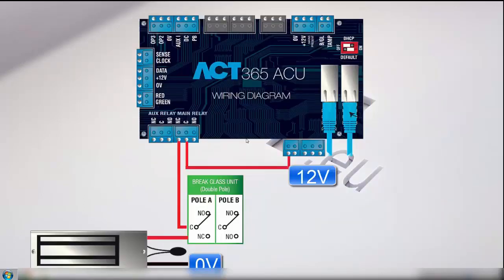We will now look at wiring the break glass detection. This is very useful for triggering the auxiliary relay to fire a sounder or a strobe in the event the break glass is pushed. Break glass detection input is looking for continual zero volts. When the break glass breaks this input the door status will report and if configured the aux relay will fire.